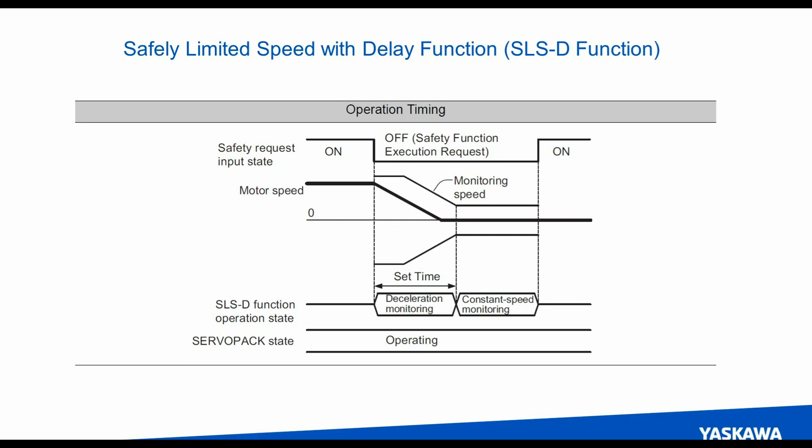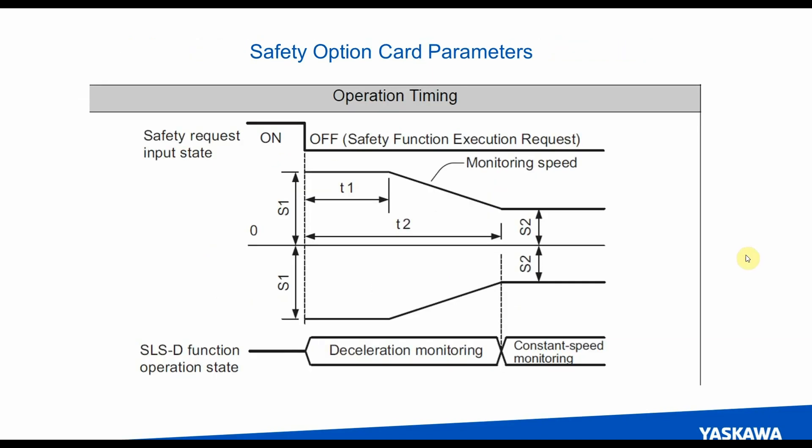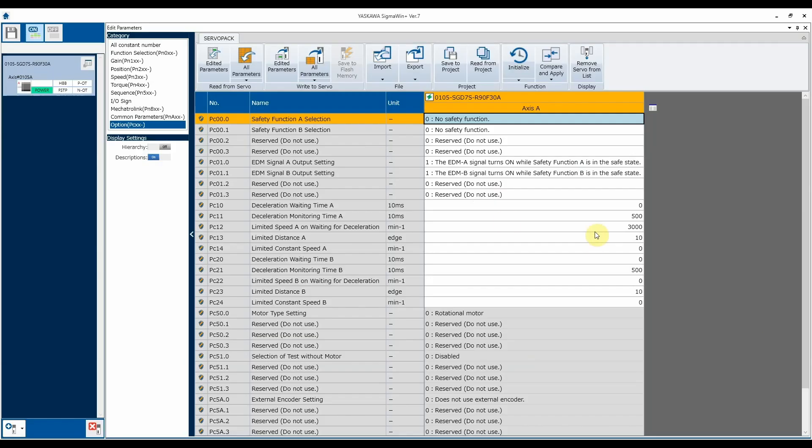It can only disable the axis. So once a safe limited speed has been requested by the safety PLC, the motion controller needs to slow down the motor with a controlled command. To know how to set up those parameters, there's timing diagrams in the manual that go over the important parameters. The way that we set those parameters is going to be through our Sigma Win Plus software. Those familiar with MotionWorks might want to know if they can get to these parameters via hardware configuration, and that's not possible. All safety parameters need to be set through Sigma Win Plus.